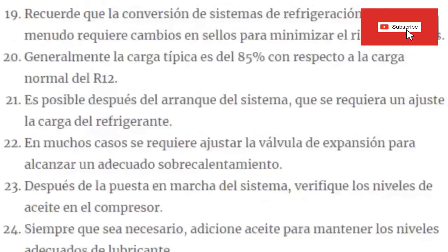20. Generally, the typical charge is 85%, with respect to the normal charge of R12. 21. It is possible after system startup that refrigerant charge adjustment may be required. 22. In many cases adjustment of the expansion valve is required to achieve adequate superheat.